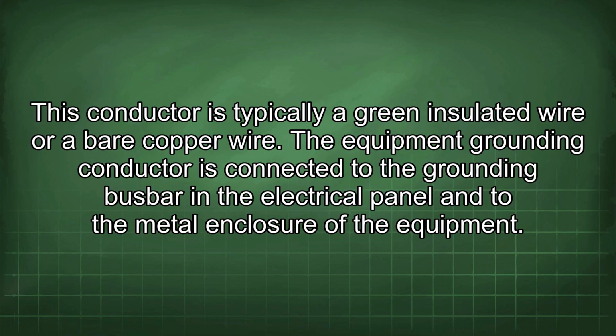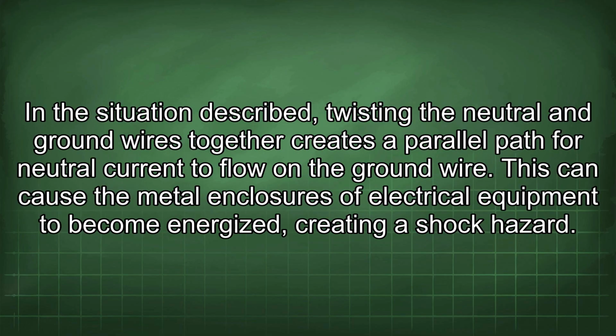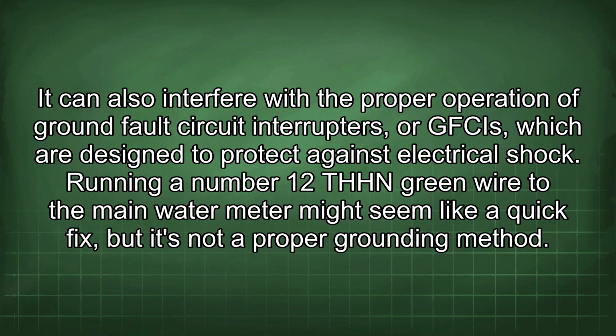In a situation described, twisting the neutral and ground wires together creates a parallel path for neutral current to flow on the ground wire. This can cause the metal enclosures of electrical equipment to become energized, creating a shock hazard. It can also interfere with the proper operation of ground fault circuit interrupters, or GFCIs, which are designed to protect against electrical shock.